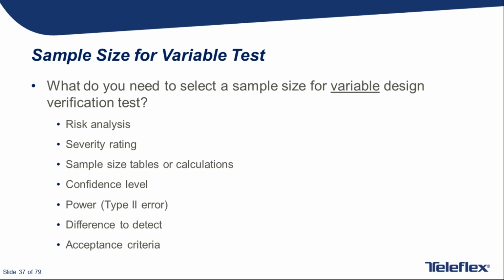Another person asks about your difference to detect, and whether it shouldn't be based on a minimum medically significant difference and not just an arbitrary value. It can be, but if you have a specification, for example 15 newtons, and you have historical data that all of your products test to be 100 newtons or something like that, the difference is so large that you can test fewer and assume a large difference to detect. But if you have a specification of, say, 15 newtons and historical data showing a population with an average of 18, then you probably better test a lot to make sure you don't get some going below 15. I think it's two different questions, and I'm answering the question about using difference to detect versus a specification, not so much test method validation, where you're looking at how accurately you're measuring something.